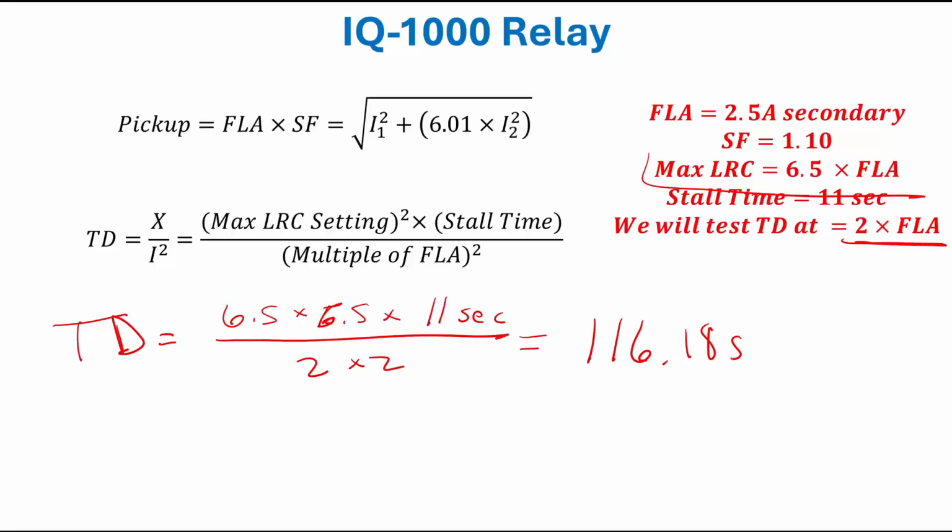So if you wanted to sit here and change some stuff, then you could. But remember, this is stall time, locked rotor current setting is squared, and then your multiple of FLA squared. There is no service factor. And in the next one, we'll go over how to calculate the pickup. It's going to be absolutely ridiculous. So strap yourself in for a lot of vector math.